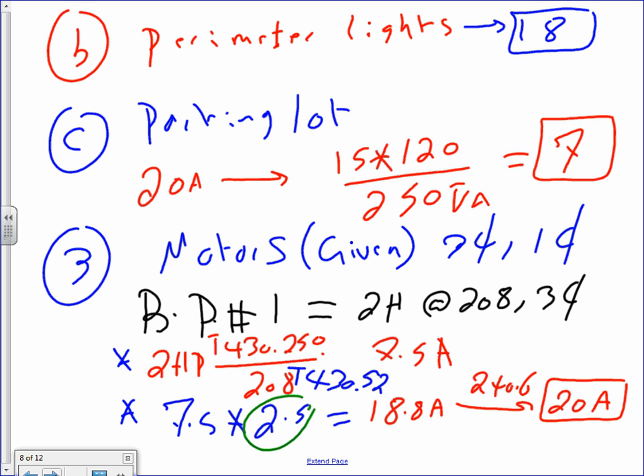Any question, guys, about this? The overcurrent protection device, 2.5. Why? Because we've done many of them. That's a dedicated circuit. Do we group them? If they are 20 amps or less, you can group them. But do we put multiple fans on one circuit? Not a good idea, not design-wise. Any question, guys, for this motor? Typical motor I picked up.